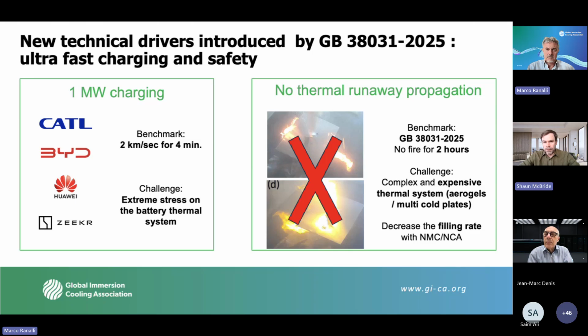And this really creates the requirement of preventing thermal runaway propagation. That is to say, if one cell is triggered for some reason, that this doesn't pass to the neighboring cells in the pack. So using conventional solutions, by that I mean especially cold plate solutions, we have to think about not just preventing the propagation, but also managing gas venting, for example, the actual inherent limits of the amount of heat that can be extracted from the cells through a cold plate solution, thermal interfaces, and so on. And we also have to try and prevent propagation using mostly aerogels, which is the state of the art at the moment. So this obviously results in quite a complex and expensive design, difficult to implement.